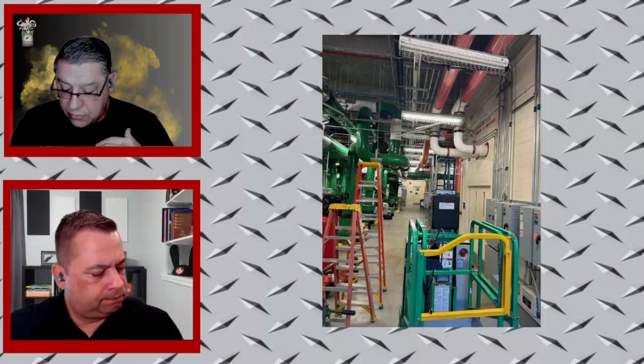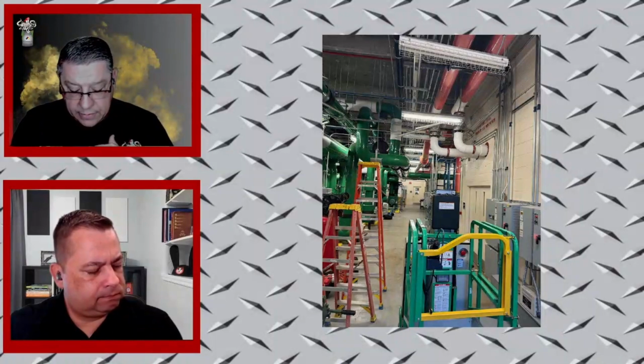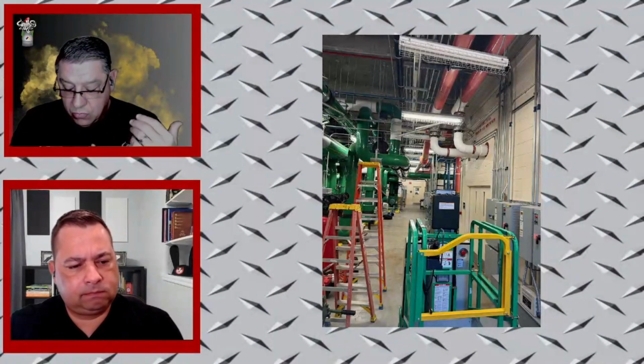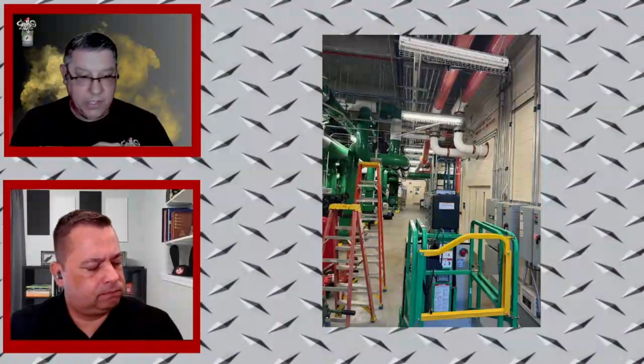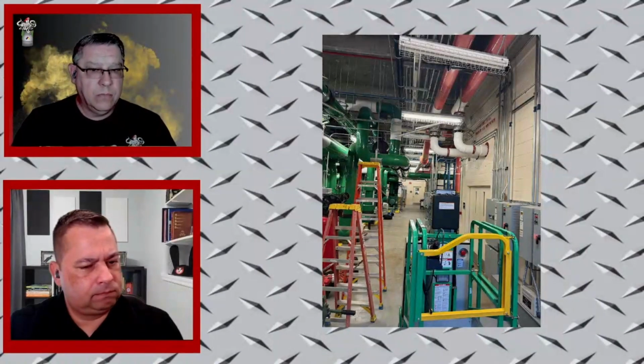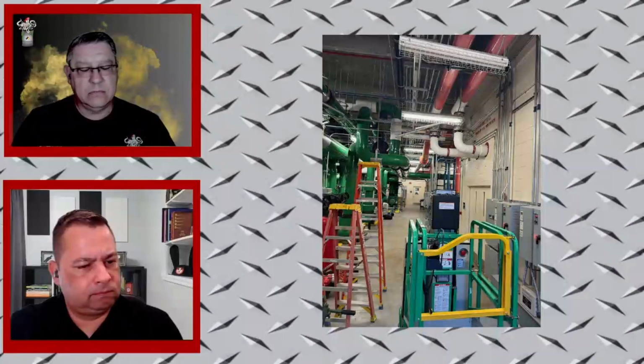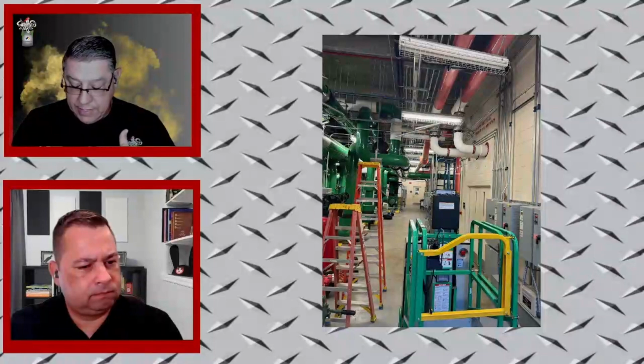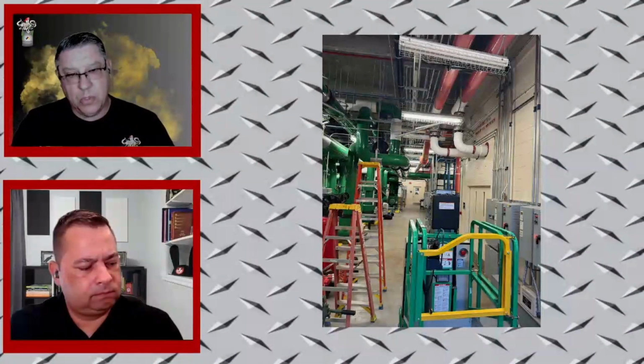After they'd done this for a little bit of time, they kept monitoring the towers. The readings for CO were approximately 10 parts per million each. So they took the scissor lifts out, they ventilated, and they went and checked the area again for where the boiler room was. They were still getting slight readings.